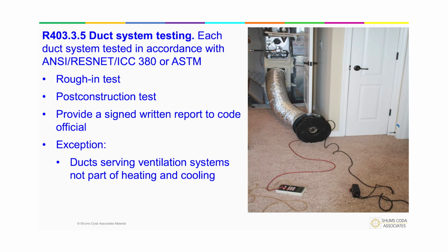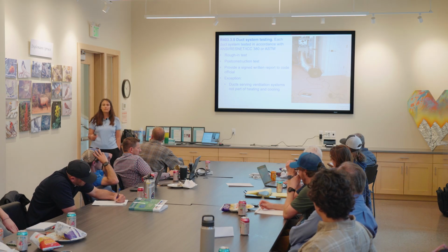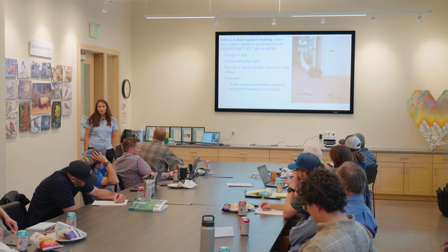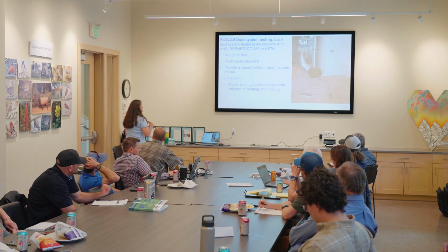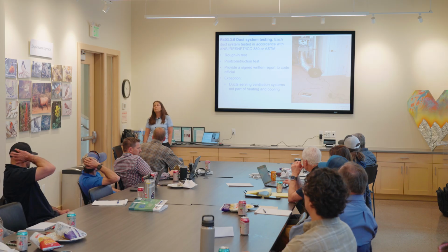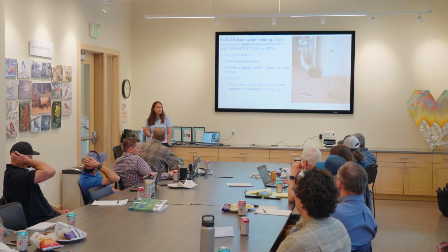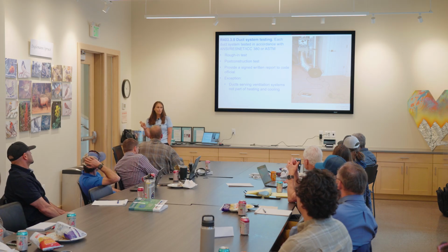Now, there is an exception. The exception is dealing with ductwork that is being utilized as part of the ventilation system, as long as it's not part of heating and cooling. So this is where it's incredibly important to know, are they doing exhaust only? Are they doing supply only? Or are they doing a combination?